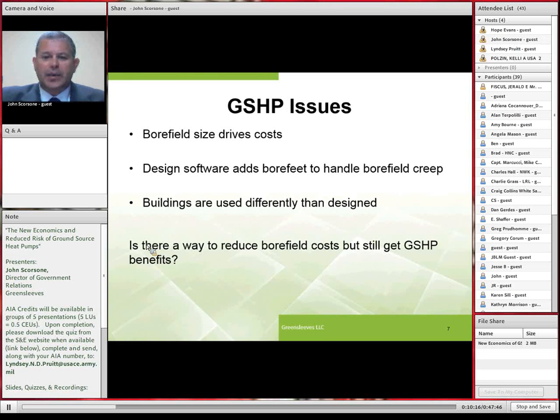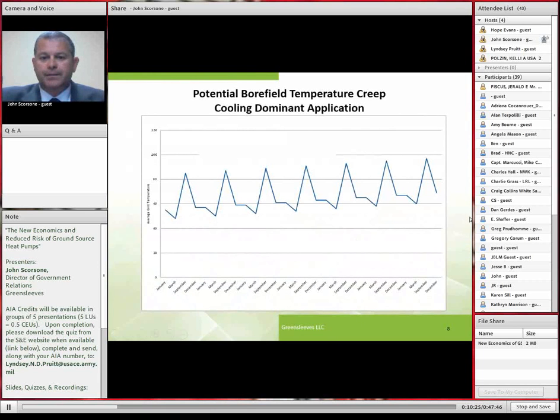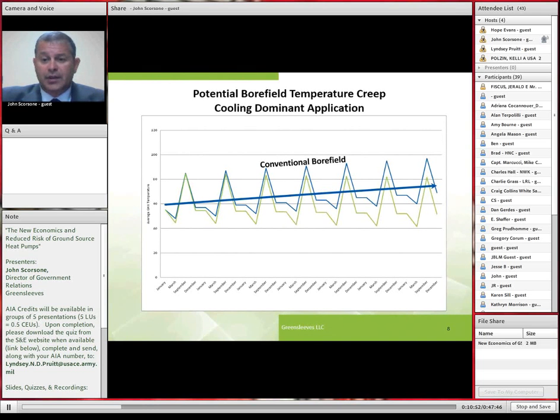So let me take a minute to talk about that bore field creep I mentioned earlier. Here's a typical bore field that is heating up over time for a cooling dominant building. The average temperature of the loop field rises, but stays within a safe operating limit for the indoor heat pump equipment. This is normal for a typical bore field installation. With Greensleeves and our GeoModule, we now control the average annual loop temperature back to first year high efficiency. By reducing the annual average temperature, we're able to downsize the bore field, and with a lower loop temperature, the bore field operates at a higher net energy efficiency ratio.